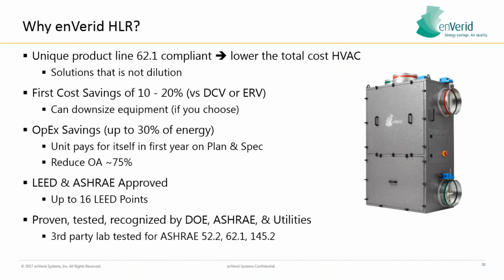So what is the enVerid HLR? Basically, our goals are to show first cost savings versus demand control ventilation or energy recovery. Under ASHRAE 90.1 and the energy cost budgeting methodology, you can actually frequently eliminate your energy recovery requirement by incorporating the HLR. And that's because essentially from a technology standpoint, we're essentially a 100% efficient energy recovery vehicle. So that's pretty interesting. And we're also driving outside air minimums typically below that 5,000 CFM of outside air requirement in many buildings to reduce the energy recovery requirement as well.